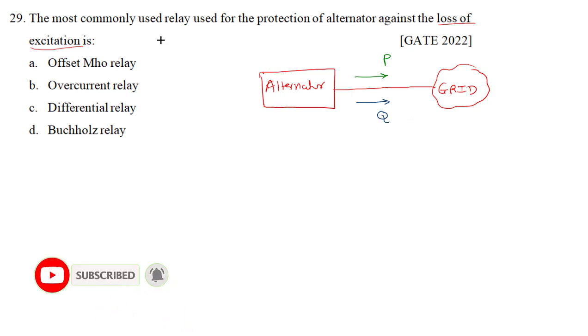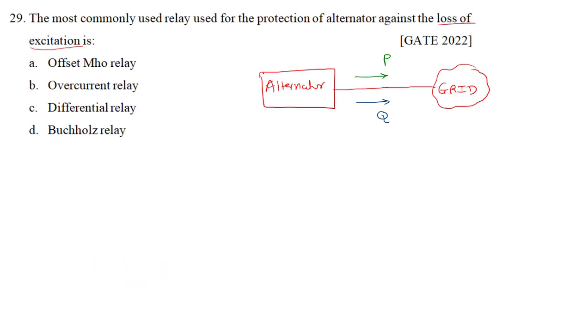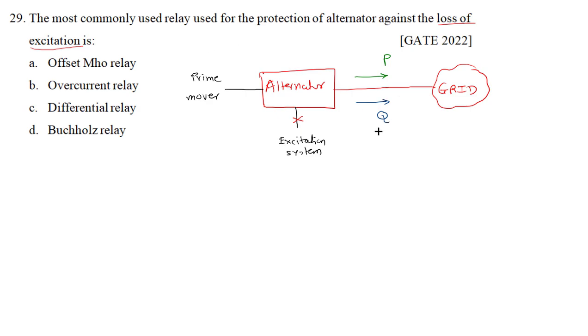Now when there is a failure of excitation, the alternator has two inputs: one from the prime mover, and the field winding supplied by the excitation system. If this DC excitation fails, it will not supply reactive power to the grid. Instead, it will take reactive power from the grid — so the direction of reactive power reverses.